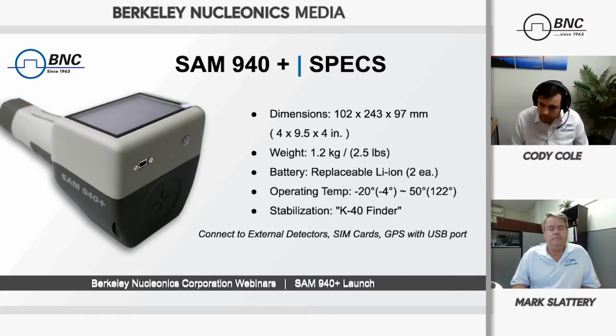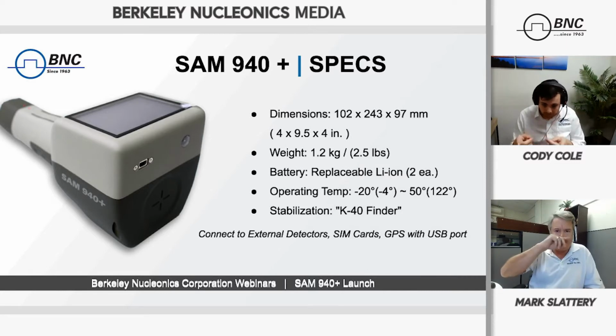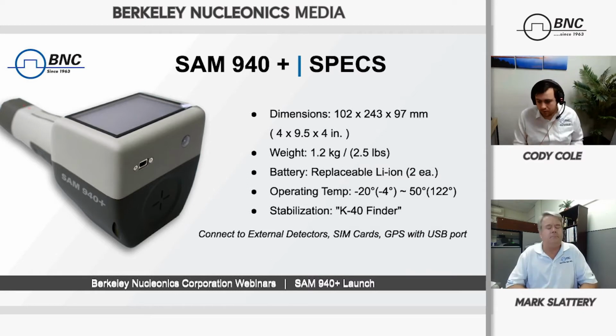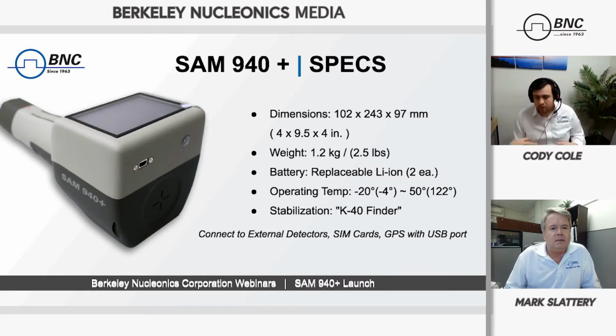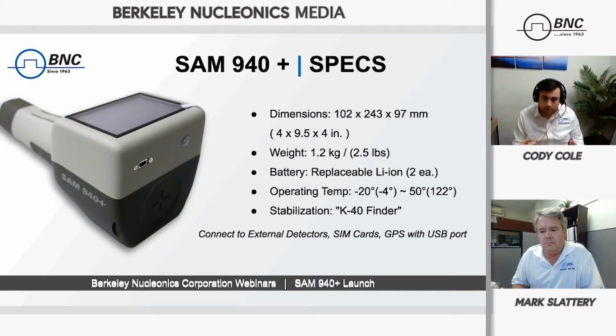One thing I want to pick out particularly on this slide is the external detectors. With our SAM iterations, we've been internalizing the detector into the units, like with the SAM 950, because when you ruggedize it like this, it protects the detector when you're out in the field. But there are medical applications or nuclear physics applications where end users prefer that the detector is external, which is something the SAM 940 had.